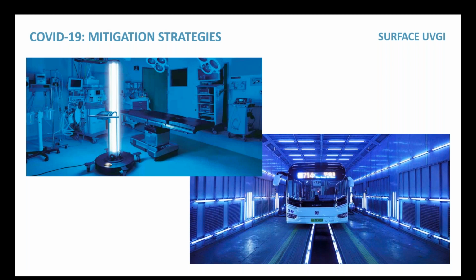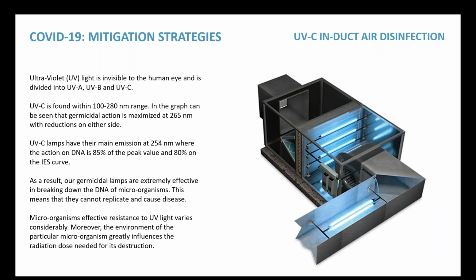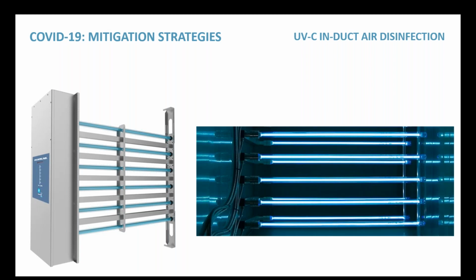There's surface UVGI, which we kind of mentioned before when we were talking about the whole idea of surface disinfection. These, when you're looking at sort of a commercial building or maybe the building types that we're looking at most frequently, aren't necessarily coming into play. However, they absolutely have their applications in healthcare situations where you're trying to truly sanitize an entire room. But really the applications that we've been seeing the most and having the most discussions about and getting the most questions about are these in-duct or in-air handling unit air disinfection systems. And essentially these are UVGI systems that are put into either some space that's available in an air handling unit or put directly into the duct to try to neutralize some of the virus particles that may be in the airstream. So you see here, these are a couple different examples of the tube type UVGI systems that can be placed in an air handling unit or in a duct.